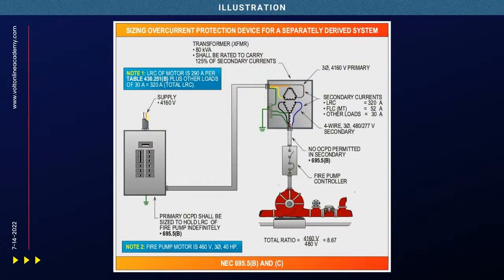A quick question. This is a stupid question, but this is from one of our users on another site. They're saying, do you have to selectively coordinate for that application so that your overcurrent device doesn't trip at that 600%? Well, no, you're not selectively coordinated because you're sizing it based on the locked rotor current. In other words, it's going to hold indefinitely.